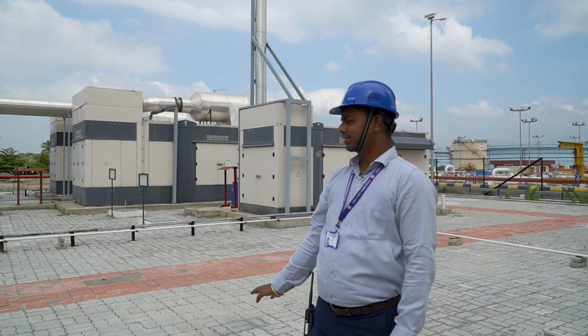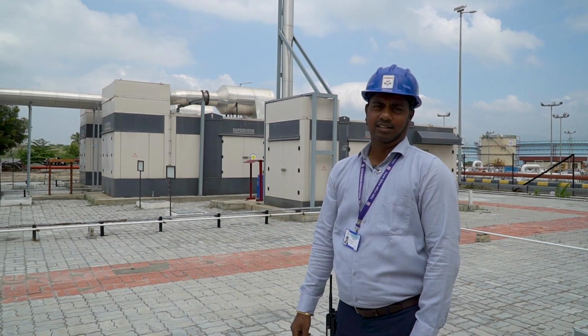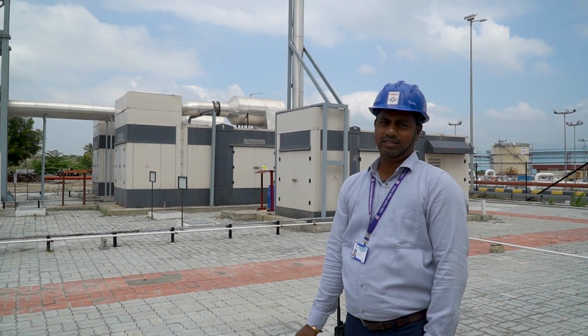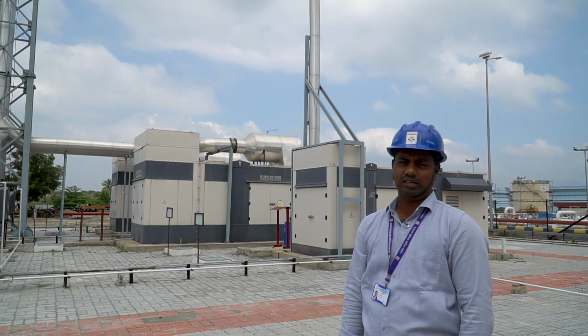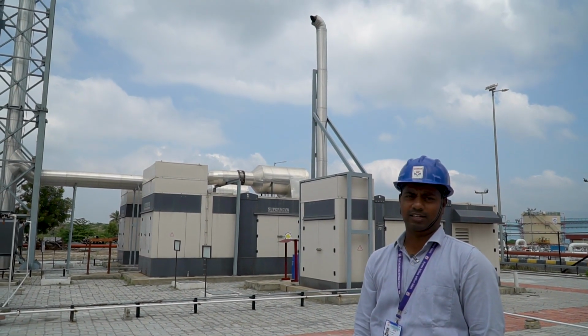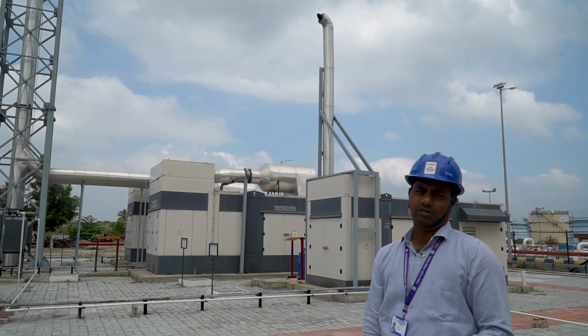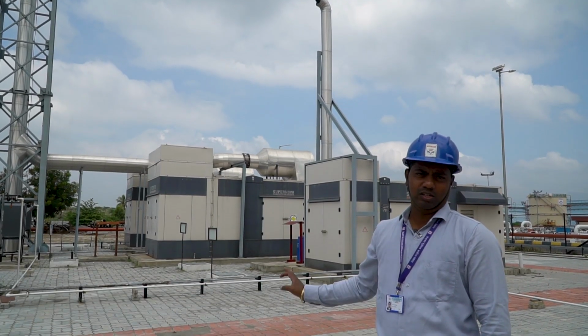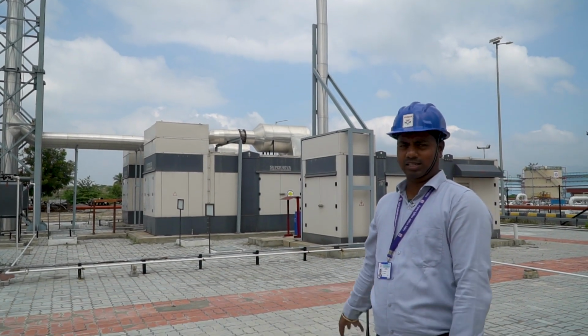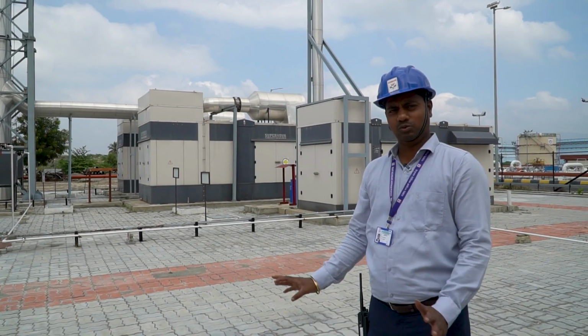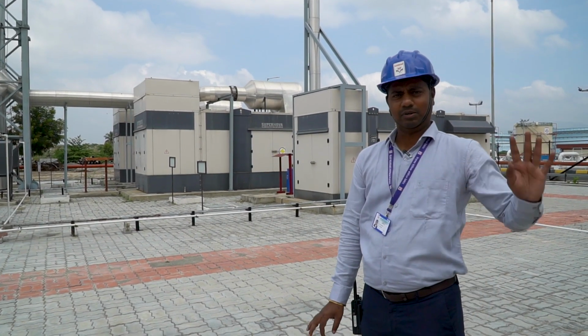So presently we are at the DG set area. We have two main DG sets of 1250 kVA and one emergency DG of 400 kVA. When regular power supply is not available, they operate automatically.